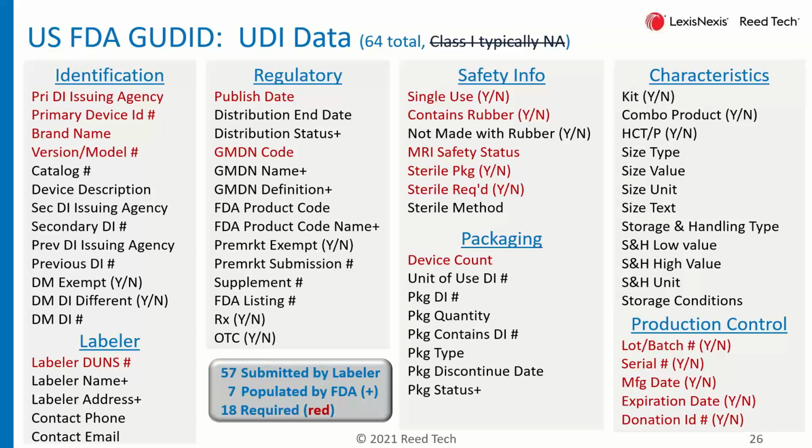there's a number of data attributes that need to be reported to the GUDID. So this is the full list that we have in front of us. The difference on this particular screen is that some of those have a red font to them, and they would be required. So those obviously are always in play. And then there's a number of these that are not typically used, and we're striking them out for a Class I. So obviously you don't have a pre-market submission number, you don't have a supplement number for Class I, and that's 510K exempt. So some of these are obviously you need to consider them. Over in the left-hand side, the direct marking Patti just mentioned would not be applicable.